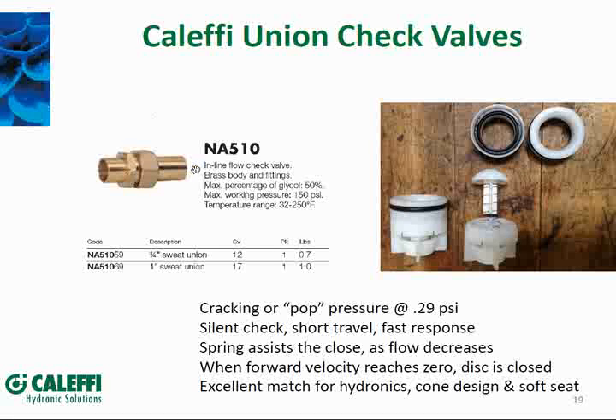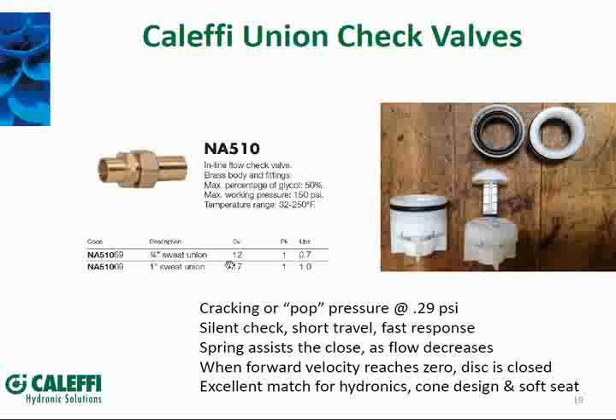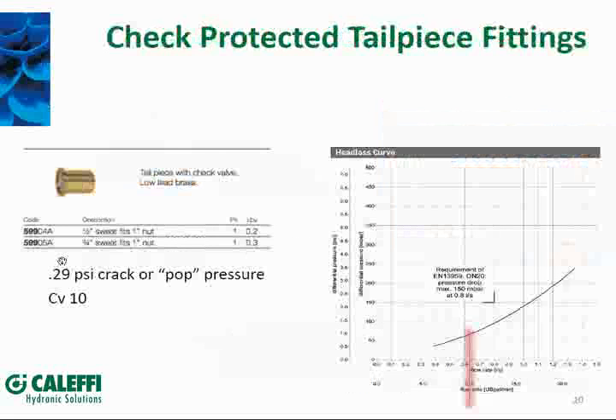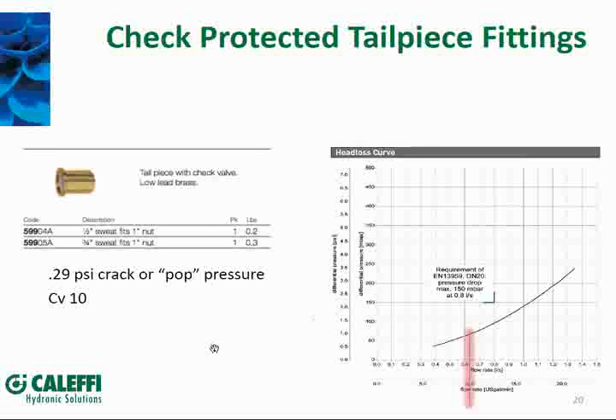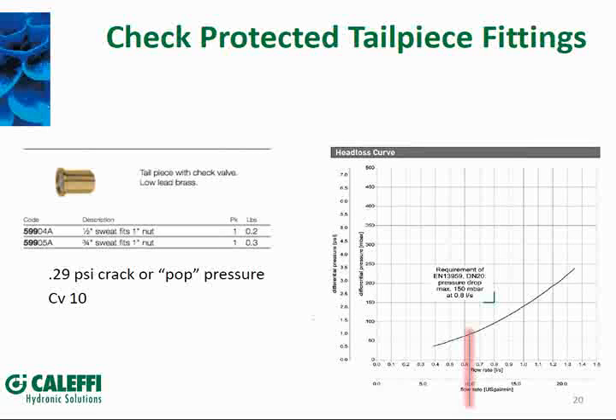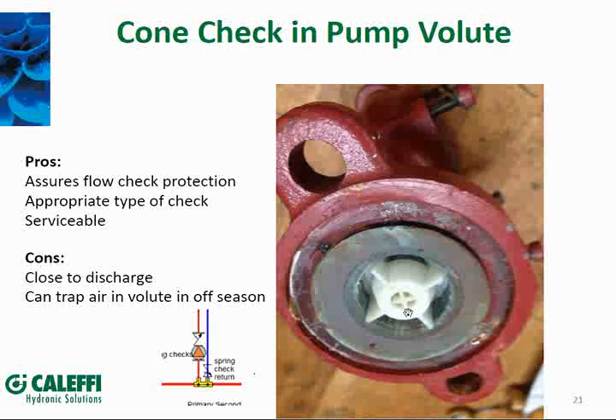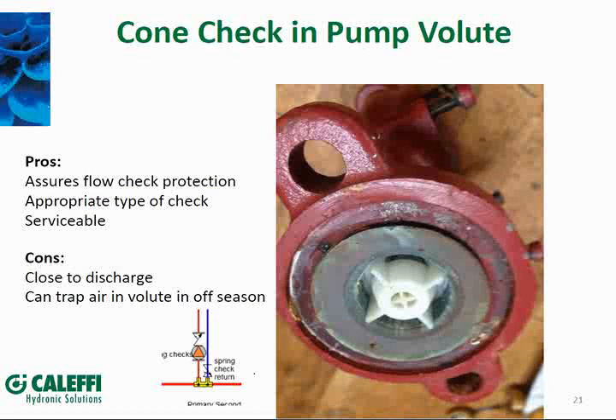What we did is make this available in a union configuration — solder it into the system first, then install the check valve so you don't melt it. You've got the ability to open it up for servicing. The flow rates are good: CV of 12 and 17 in the two different pipe sizes, all brass construction. This is the type of valve I'd encourage you to use — a soft-seated, cone-shaped check valve with spring assist. It's also built into many different devices; many pumps come with the check valve built in, and you can remove it if an application doesn't need it.